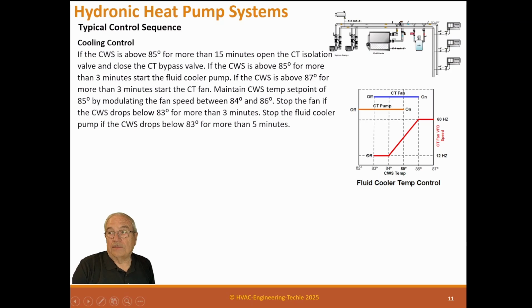So here's the deal. If you look at this, if the condenser water is cold and it keeps heating up, and it gets to 85 degrees, and this cooling tower pump comes on, and we start circulating water through the cooling tower, which will start to provide a little cooling effect on the heat exchanger. Not a lot, but a little bit. So if the temperature continues to rise and it gets to 86 degrees, then we enable the cooling tower fan, and it starts to run.